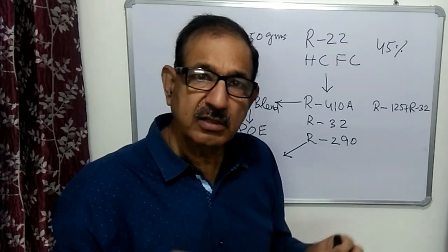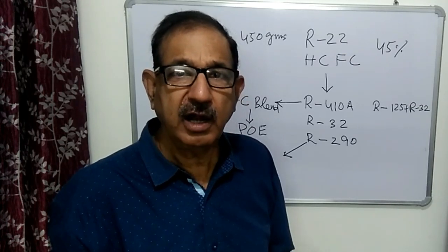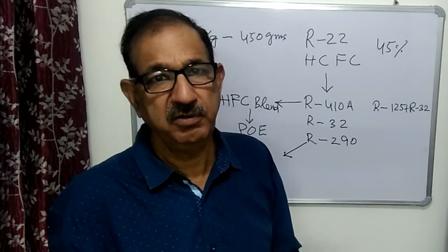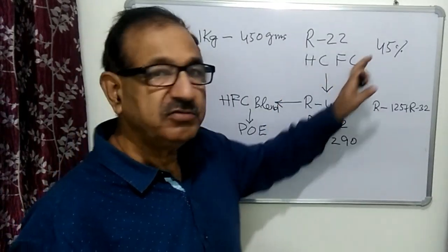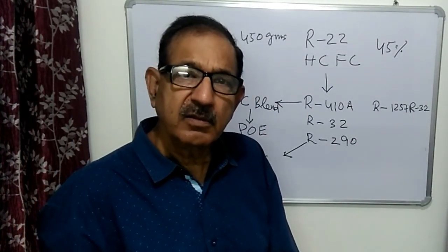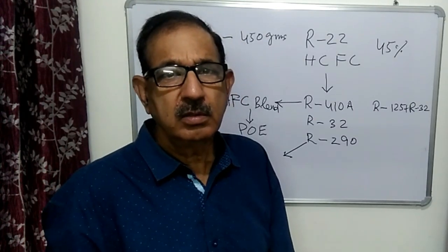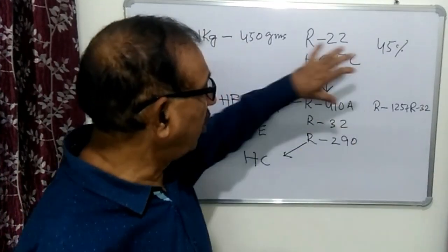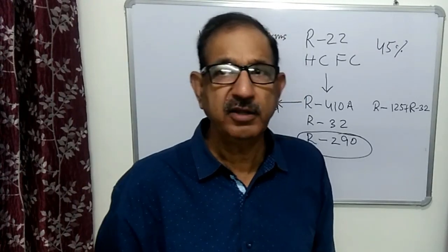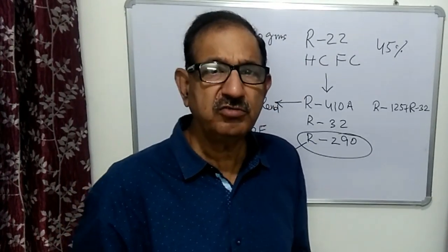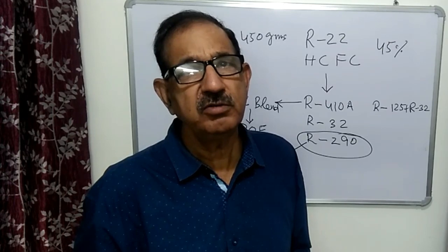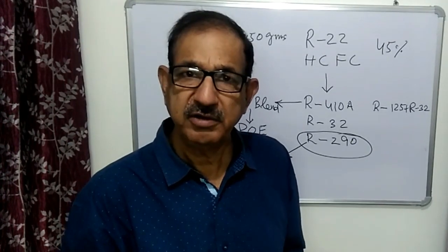Because R290 has the same pressure as R22 and the charge quantity is only 45%, the load on the compressor goes down, which increases the life of the air conditioner and gives better results. This refrigerant also has very low GWP and no ODP, making it a long-term refrigerant. Currently Godrej is using R290 in India, but in the coming years all companies will have to switch over to R290.